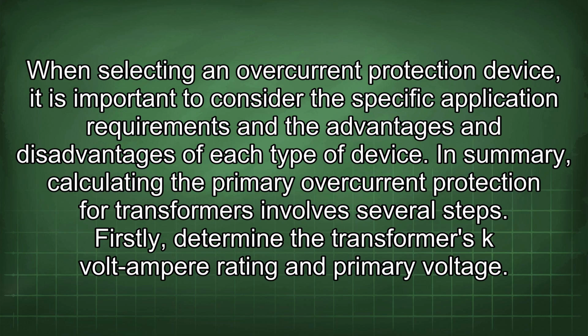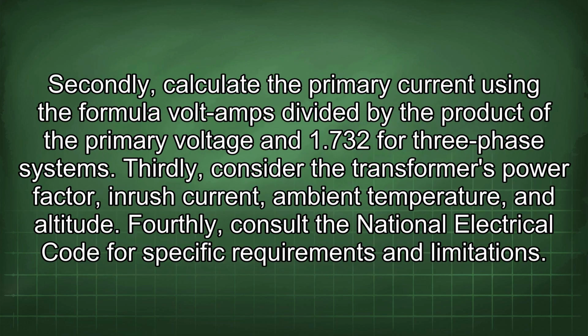In summary, calculating the primary overcurrent protection for transformers involves several steps. Firstly, determine the transformer's kVA rating and primary voltage. Secondly, calculate the primary current using the formula: volt-amps divided by the product of the primary voltage and 1.732 for three-phase systems. Thirdly, consider the transformer's power factor, inrush current, ambient temperature, and altitude.